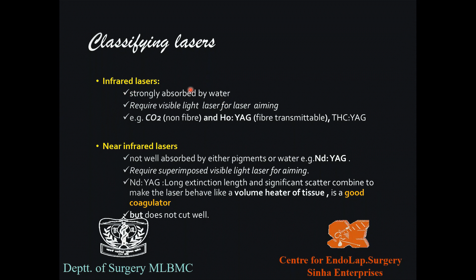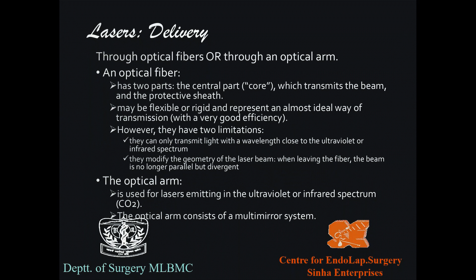Near infrared lasers are neither absorbed by pigments nor by water, and they also require a superimposed visible light for aiming since they too are invisible. The most common example is the neodymium:YAG laser, which has a long extinction length and significant scatter. Because it is not absorbed by water or pigment, it scatters, making it behave like a volume heater of tissue — a good coagulator but not a good cutter.